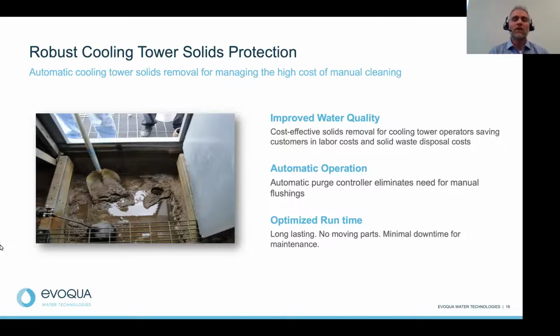Now, hydrocyclone separators are really the robust workhorse, as I mentioned earlier, for providing automatic solids protection within a cooling system. Improve water quality. Right? We're really removing sand, very large, heavy debris from a cooling system that allows operators to avoid the associated manual labor, shoveling out tower basins, exposing your staff to various different health hazards, and even potentially the high cost of solid waste disposal. That can add up quite quickly over the course of your operational season.